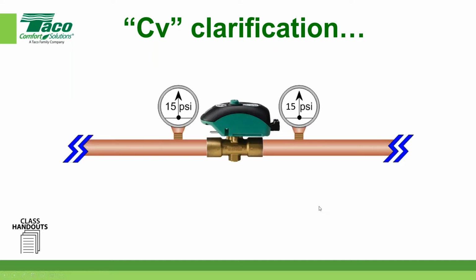So again, this gives you a visual of the same thing. If I'm sitting static, that means the pump's not running, no flow, just sitting there, and I've got 15 pounds on each side of this valve. And all of a sudden, on the test bench, I can turn up my GPM incrementally until I get to the point where I see 1 PSI. Then I look down here and see what GPM that is at a 1 PSI drop across the valve. That becomes the flow coefficient, or CV, of that particular valve.